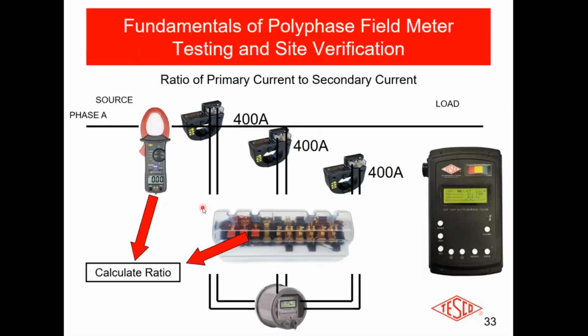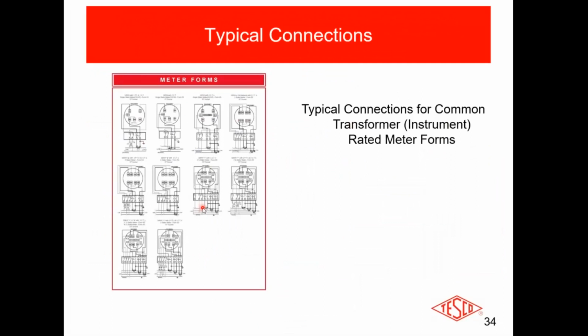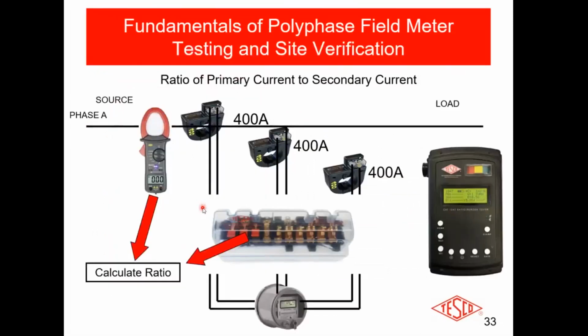So when you go out there, what you're checking for is the ratio. Are you looking for a highly precise number? No. You just want to make sure that it's roughly 400 to 5. So if I go out there and I'm reading 80 amps, I want to make sure that I'm getting about 1 amp on the secondary, roughly. I could be off by 5 or 10% because we didn't make a 390 amp to 5 CT. We made 100 to 5s, 150 to 5s, 200 to 5s, 300 to 5s, 400 to 5s. They're fairly widespread. So you just need to get in the ballpark. All right?